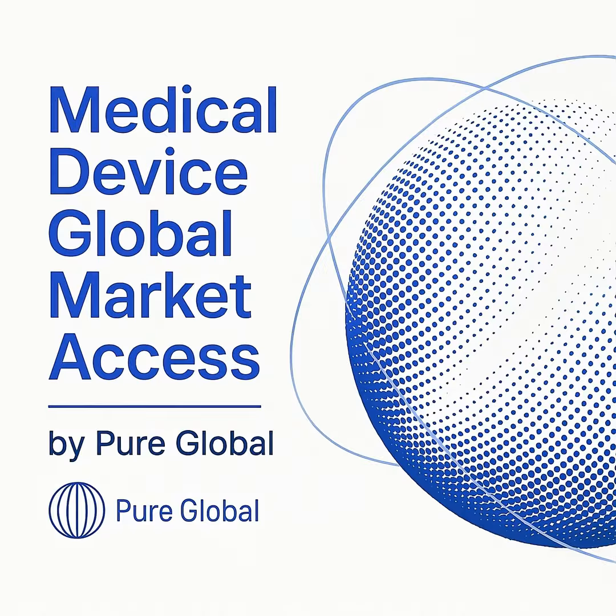The classification assigned to your device is more than just a label. It dictates the entire regulatory pathway. It determines the necessary content for the technical dossier, known as the ASEAN Common Submission Dossier Template, or CSDT, the required level of evidence for your quality management system, such as ISO 13485 certification, and the degree of scrutiny your submission will face from the HSA.